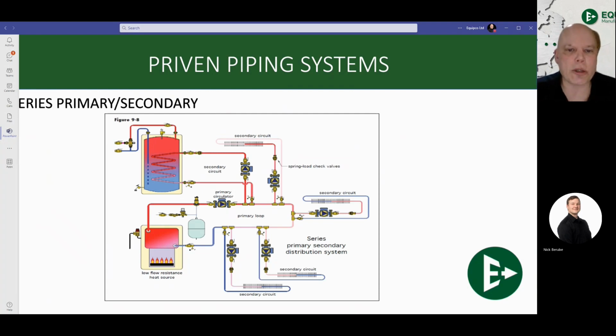Moving down the line, we get into our first real primary secondary piping system, where your primary loop is the one coming off the boiler and then back into the boiler. All of our secondaries are going to be pulled off of your closely spaced tees. And again, the rule for closely spaced tees is no more than 4 pipe diameters apart from each other, and that follows the rule of physics that what goes out must come in when we're talking about flow.